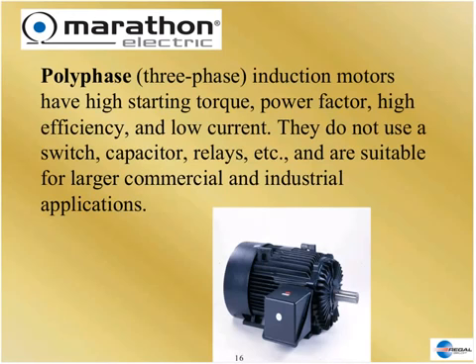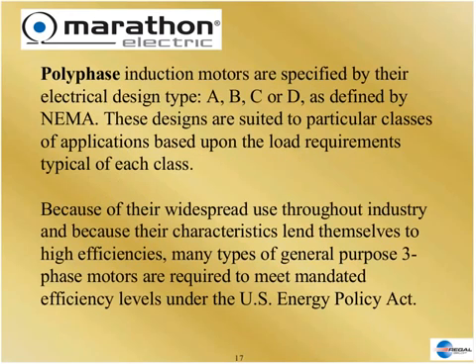Polyphase motors can always start — they know how to run and don't need any help. They are the workhorse of large commercial and industrial applications and are very efficient, much more so than fossil fuel engines. We describe polyphase motors by their design type: Design A, B, C, and D, defined by NEMA — the National Electrical Manufacturers Association — based on the shape of the speed-torque curve.